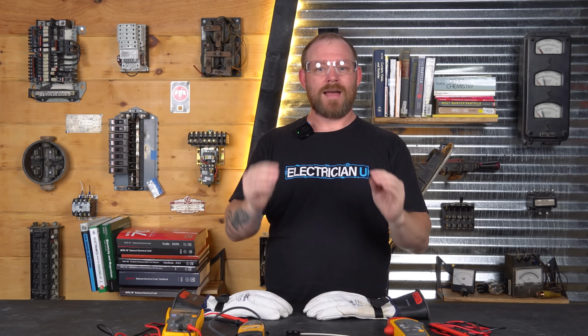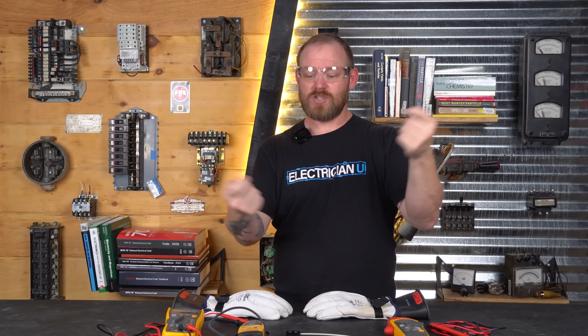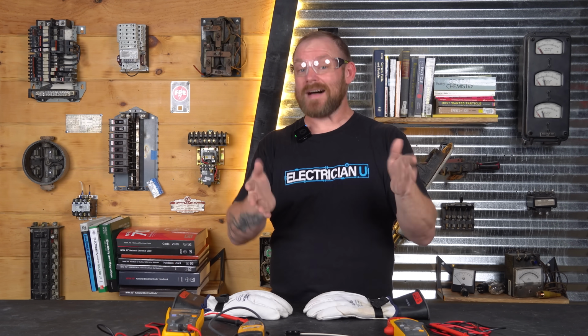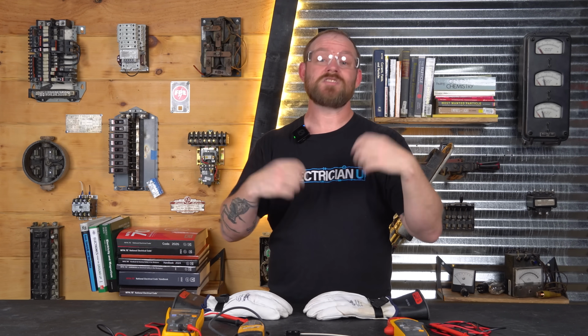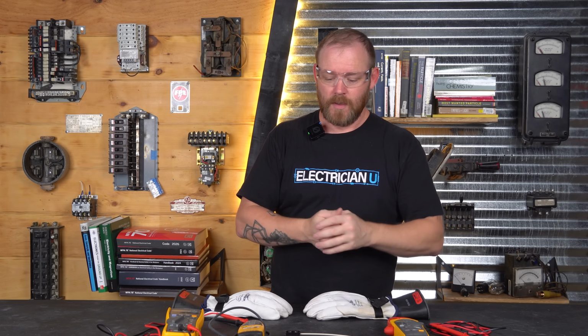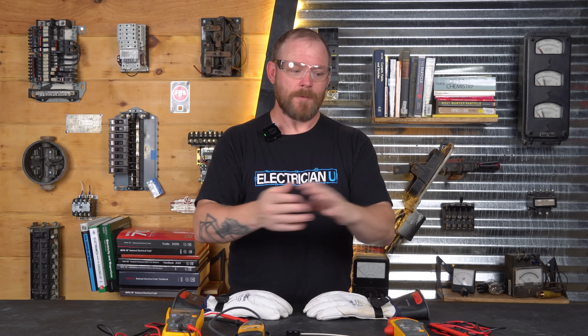But typically for you to have a drastic change in voltage and for you to be testing between things and just get a bizarre voltage, a lot of times that is a ghost voltage. It's not a true voltage. What I mean by true voltage is something that is connected to a source that can actually push current through a load. So like power behind a voltage, right?